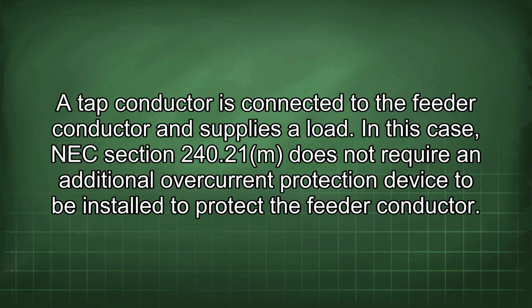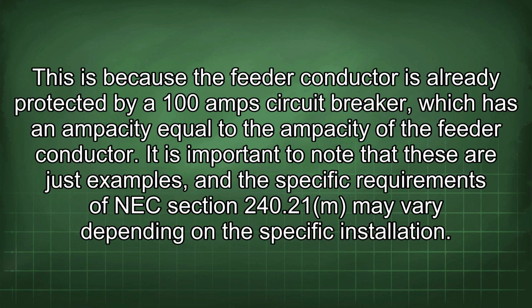In this case, NEC Section 240.21 does not require an additional overcurrent protection device to be installed to protect the feeder conductor. This is because the feeder conductor is already protected by a 100 amp circuit breaker, which has an ampacity equal to the ampacity of the feeder conductor. It is important to note that these are just examples, and the specific requirements of NEC Section 240.21 may vary depending on the specific installation.